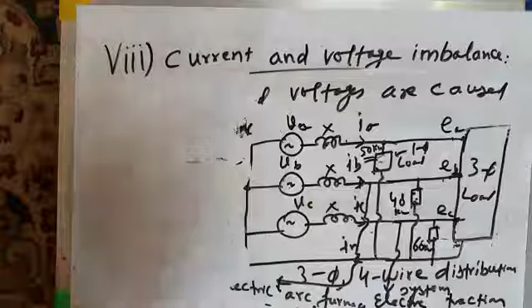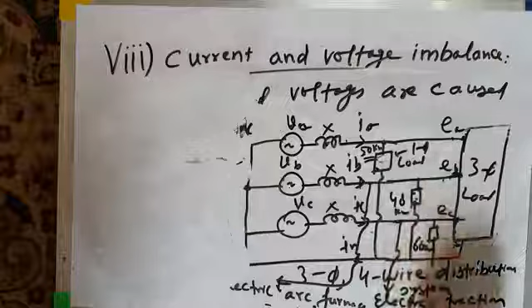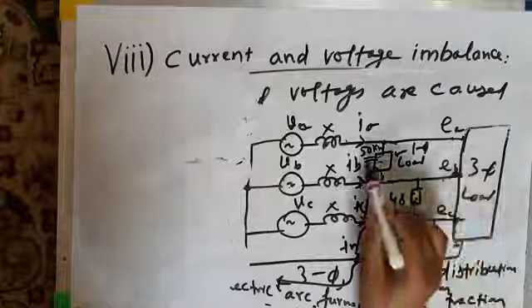So we have seen that three-phase unbalanced voltages are predominantly caused by unbalance in the load, current unbalance. And I have given you the example of how current unbalance occurs. Another cause of three-phase unbalance is single phasing. For example, you have a three-phase induction motor and one of the phases blows, its fuse has blown. So the motor gets supply from only two lines. This line is gone. So this also results in unbalance.